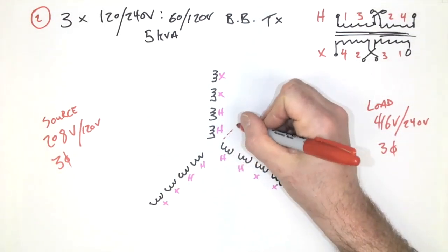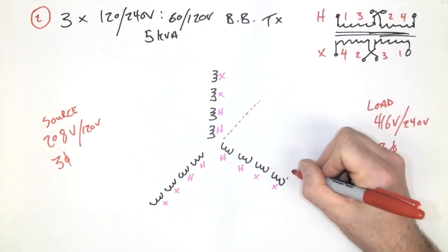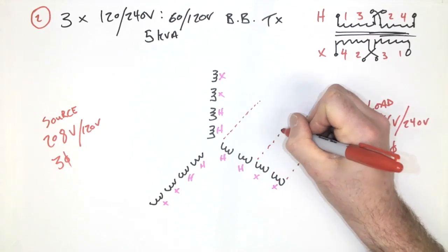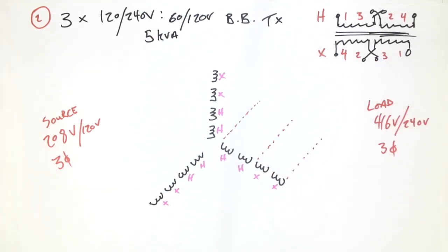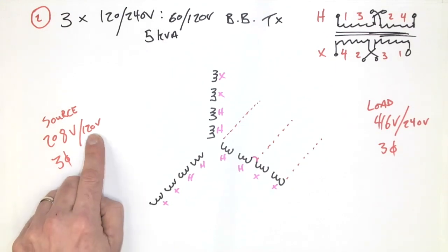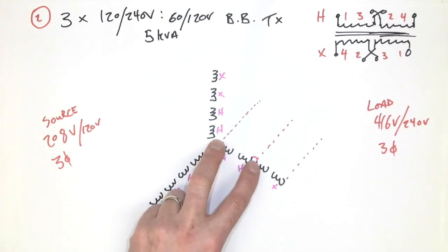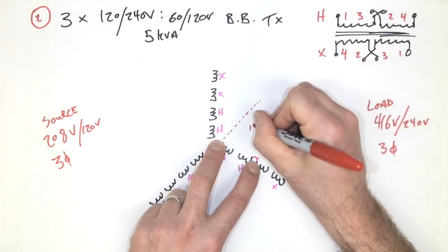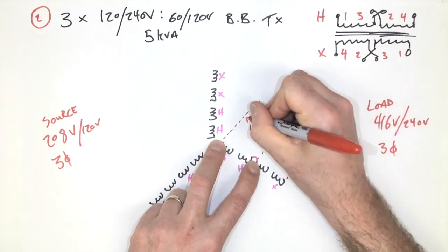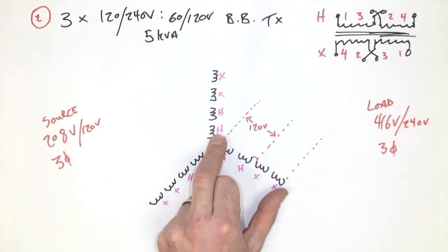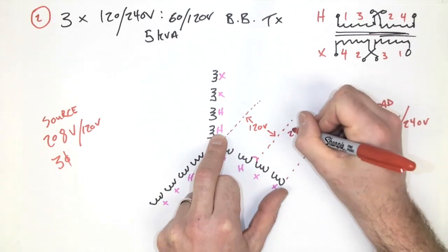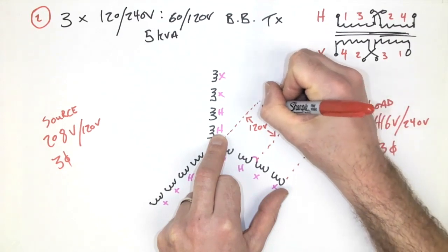I'm going to do the same thing I did on the previous one. I'm going to draw a dotted line here and here, and from the middle. Now remember, we've got a series connection that is going to connect the high and the low voltage windings together. The low voltage or incoming value of voltage is going to be 120 volts, and that would be from here to here. So I'm just going to put 120 volts. The voltage that I need from here to here is going to be 240, so that's from here all the way up to here.